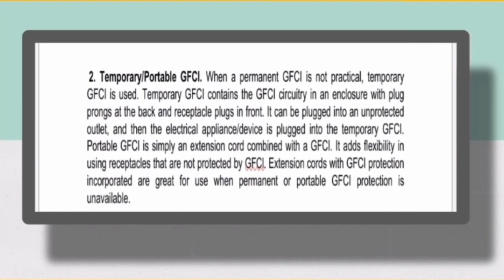Number two: Temporary or Portable GFCI. When a permanent GFCI is not practical, a temporary GFCI is used. Temporary GFCI contains the GFCI circuitry in an enclosure with plug prongs at the back and receptacle plugs in front. It can be plugged into an unprotected outlet and then the electrical appliance or device is plugged into the temporary GFCI. Portable GFCI is simply an extension cord combined with a GFCI. It adds flexibility in using receptacles that are not protected by GFCI. Extension cords with GFCI protection incorporated are great for use when permanent or portable GFCI protection is unavailable. To understand more about portable GFCI, watch this video.